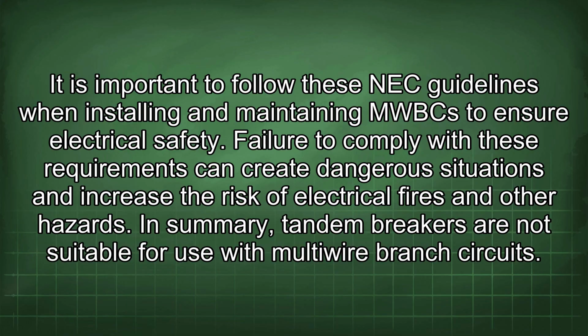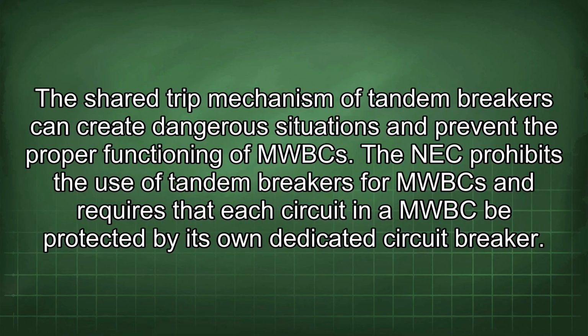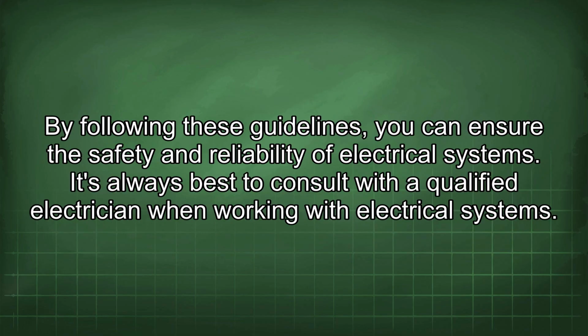In summary, tandem breakers are not suitable for use with multi-wire branch circuits. The shared trip mechanism of tandem breakers can create dangerous situations and prevent the proper functioning of MWBCs. The NEC prohibits the use of tandem breakers for MWBCs and requires that each circuit in MWBC be protected by its own dedicated circuit breaker. By following these guidelines, you can ensure the safety and reliability of electrical systems. It's always best to consult with a qualified electrician when working with electrical systems.